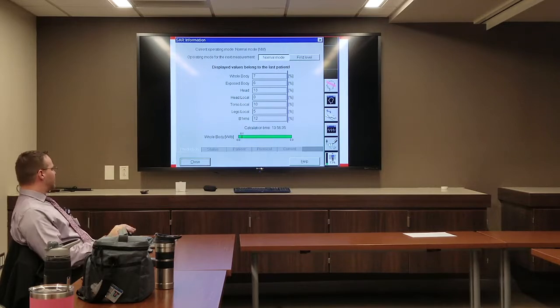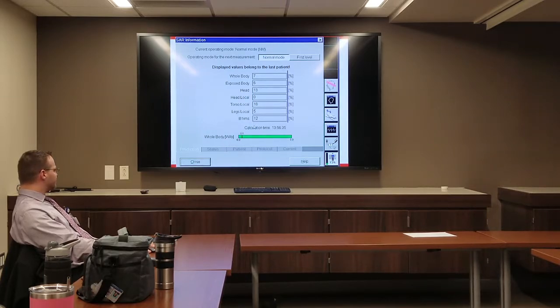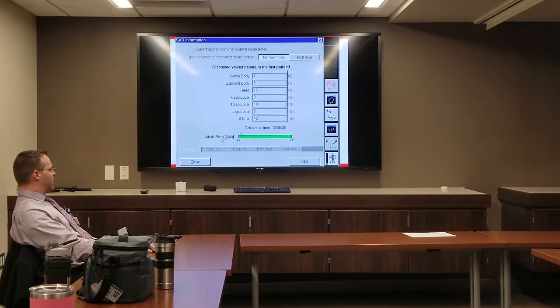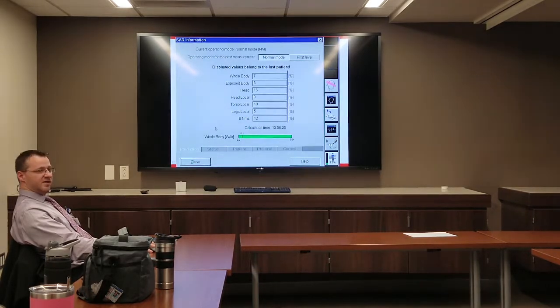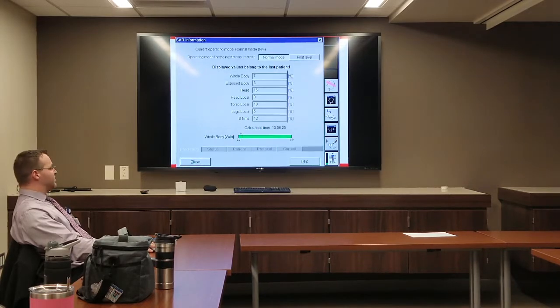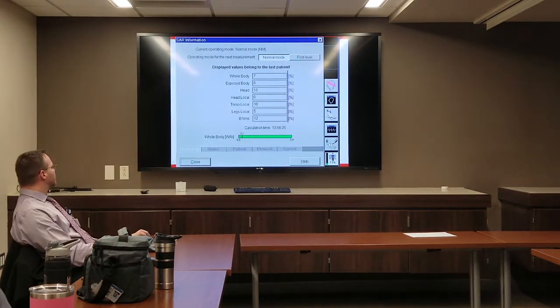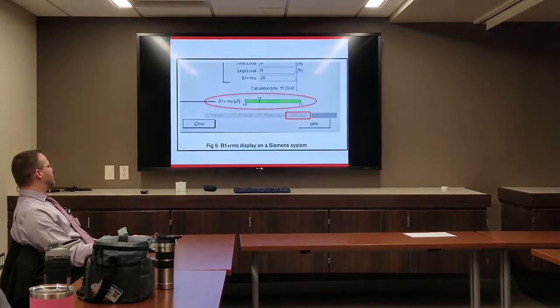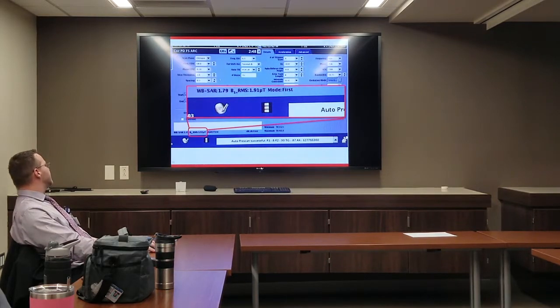On a Siemens scanner, you can see whole body and head SAR readouts on screen. You may also look at B1+RMS for some implants. If your scanner is set to pounds for weight entry, it will give you the wrong readout — you need a conversion chart. Newer scanners can be set to metric in the settings, which will display values in watts per kilogram. B1+RMS is measured in microtesla. On GE scanners, whole body SAR and B1+RMS in microtesla are shown at the bottom of the screen.